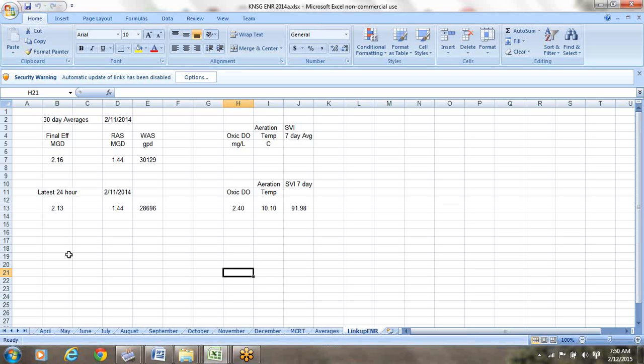Like what happens if a DO probe, which we are looking at, is not in the basin but up in the air and giving you a high DO reading, or a value called NAN. How do we handle that? Well, we have code which filters out those and allows IVops to still operate.